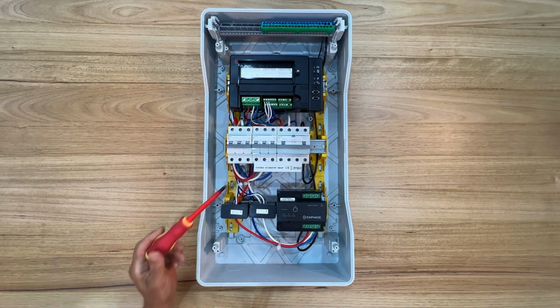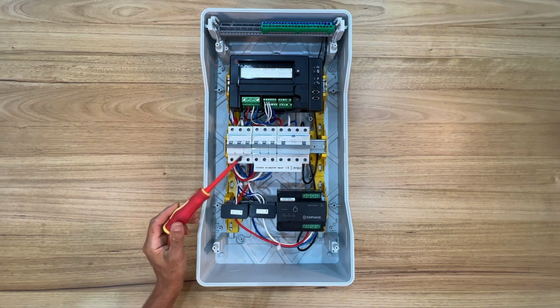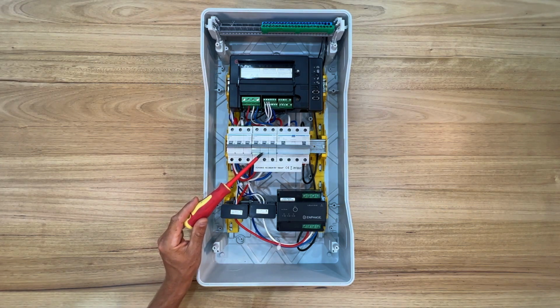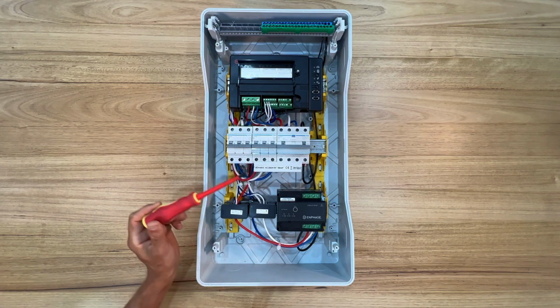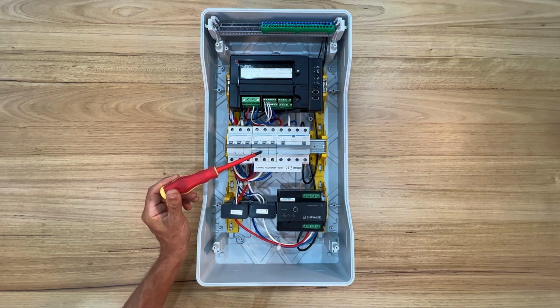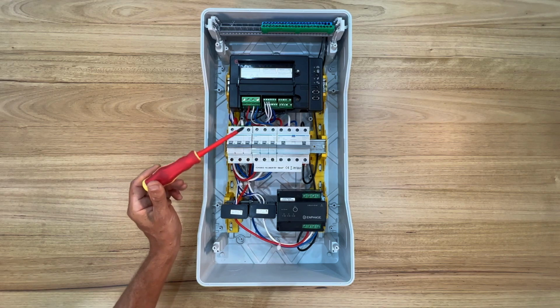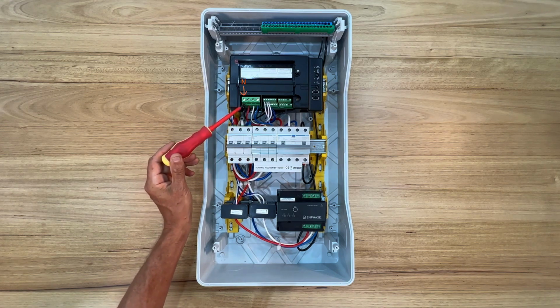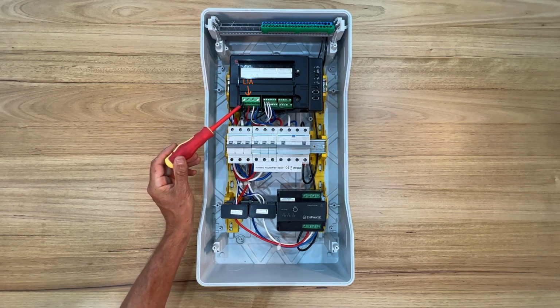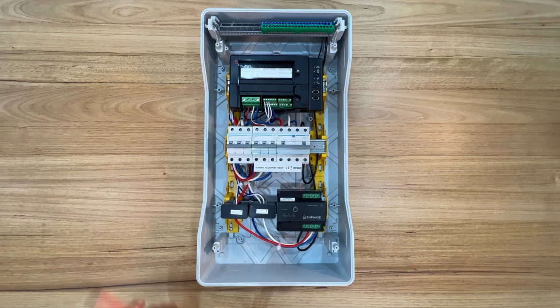Here is the main isolator for the subboard. Adjacent is the power supply to the IQ gateway. The example uses a 6 amp 3-phase circuit breaker. Now each of the phases must be wired into the terminals of the IQ gateway. The gateway uses the phase connections as voltage reference for measuring the current transformers.